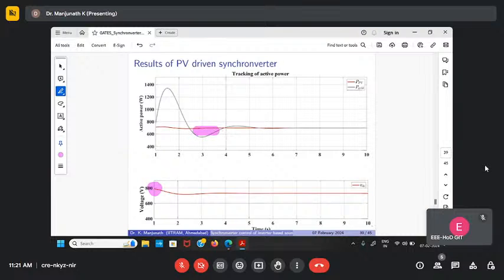These two transients also allow power to drop from the grid in the shaded region, which is not a safe option. Since it is 700 watt, you are getting a transient of 1300 watt, almost twice the defined value — if you are injecting 10 kilowatt, you are not supposed to give a 20 kilowatt surge. So this is indeed problematic, due to not having a better choice of control gains.